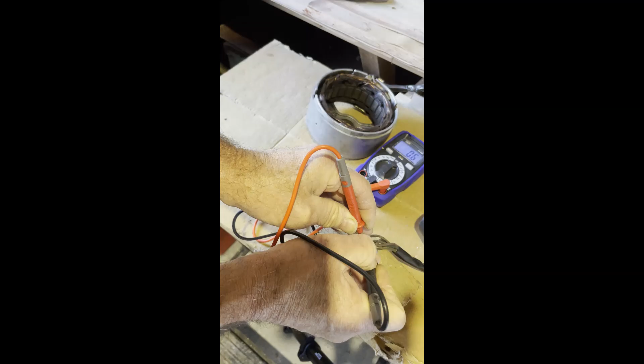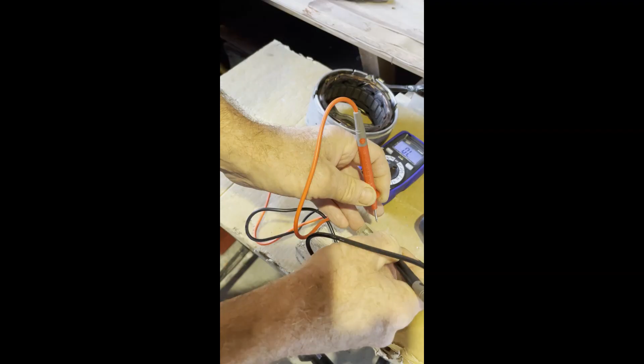Left to right, 0.5, centre to right, again 0.5 ohms. So having proved we've got continuity between all of those, you can test from any one of those contacts, but it all amounts to the same thing in this instance, since they're all interlinked. To just check down to the casing of the stator and make sure that you have got an open circuit, so that is, you're not shorting down to ground, which indeed we have.